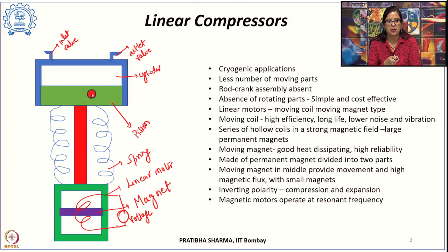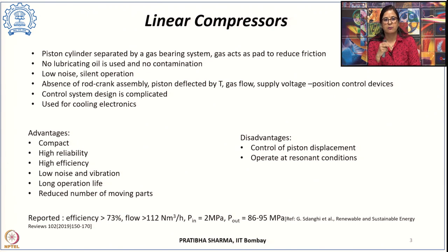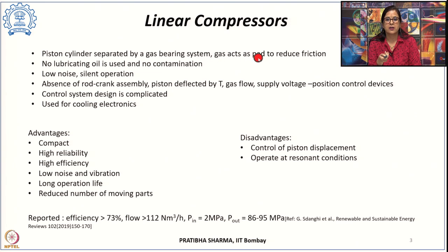The compression and suction stroke is provided by means of coupling through the spring. By inverting the polarity of the supplied voltage, we can achieve compression and expansion of the gas in the compression chamber. These magnetic motors usually operate at their resonant frequency so that ohmic losses are minimized, with direct coupling to the piston. The biggest advantage is a gas bearing system that separates the piston and cylinder, reducing friction and losses.